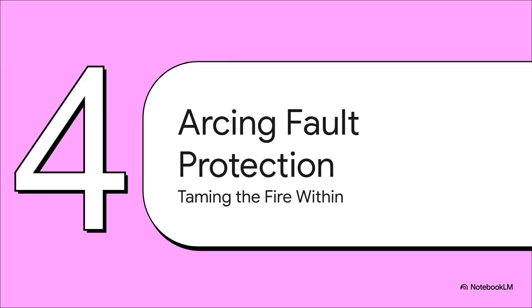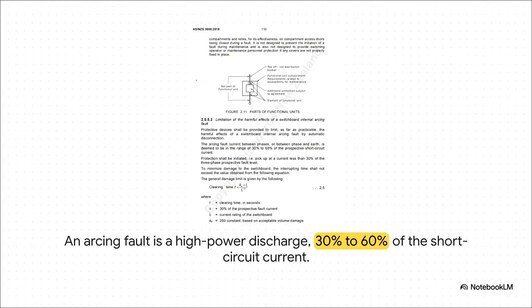All right, now we need to focus on one of the scariest, most destructive things that can happen in an electrical system, an arcing fault inside a big switchboard. We're not talking about a little spark here. This is a plasma explosion. It's an event with so much energy it can vaporize copper busbars in the blink of an eye. That's why for any switchboard rated 800 amps or more, the standard says you absolutely must have protection to automatically shut it down and limit the damage.